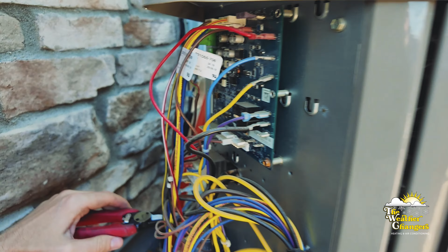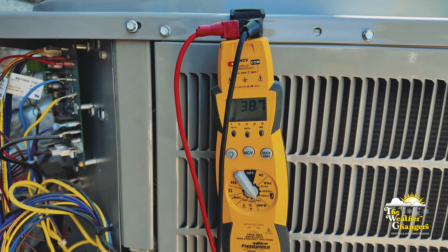First thing I'm going to do is make sure that the AC truly is off before we test. Next, I'm going to discharge this capacitor. All right, now I'm going to pull it out and we're going to test it. Here's our cap. We're going to use my voltmeter here. We're going to make sure that it's within spec. This is a 40 plus 5. We're at 39.8. That is well within spec.